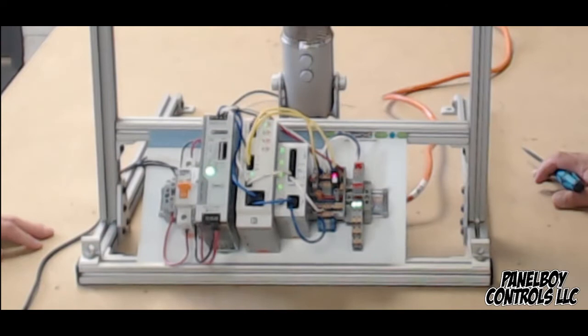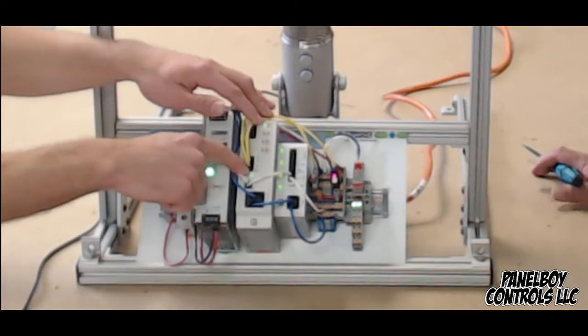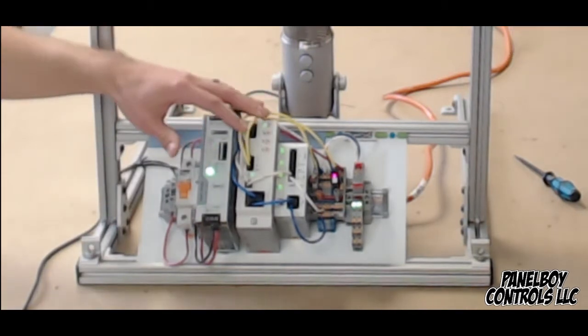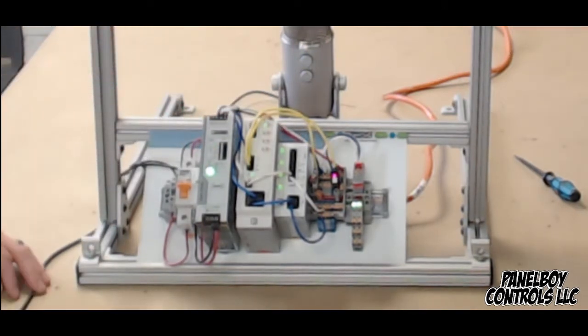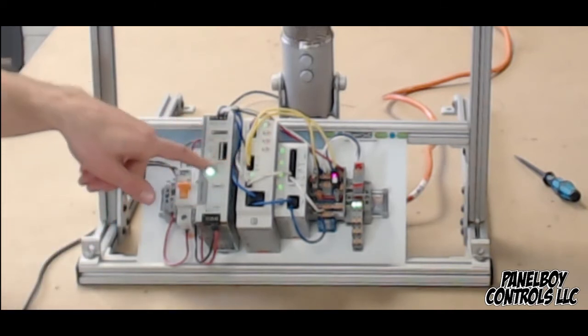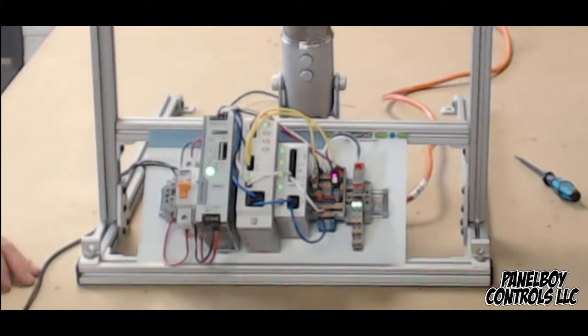What we'll switch our focus to is the one I don't have wired up, I is greater than 80%. So if I want to take this a step further and have a little bit more information coming out of this thing, I can. This I greater than 80% will let me know if a load on any one of those circuits is greater than 80% of the nominal current. Typically, it's best practice to size your circuits so that if it's going to be set to 1 amp, you're not pulling 1 amp continuously. The reason for that is nuisance tripping. It's always a bad day when a line shuts down because you're just towing the line and causing shutdowns, which costs our end users a lot of money. So that's kind of the purpose of that.